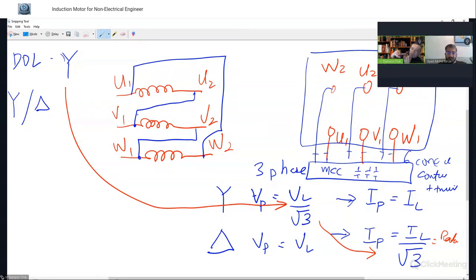Now if you go economically wise, DOL is the straightforward starting configuration. Although it is straightforward, the starting current is high. It could be 6 times full load current or 7 times full load current, right? That is why I said just now from the beginning, it is the responsibility of the electrical engineer to ensure that the motors that you have in the plant should work regardless of whatever situation.